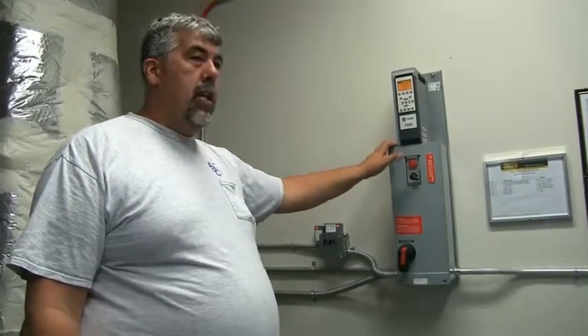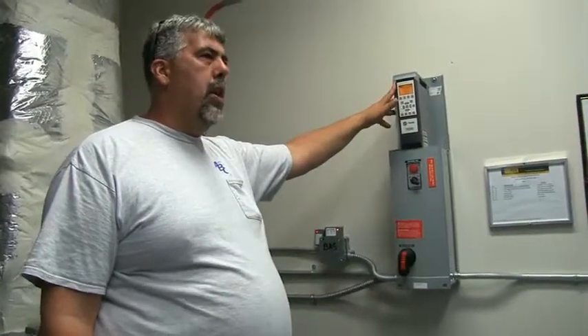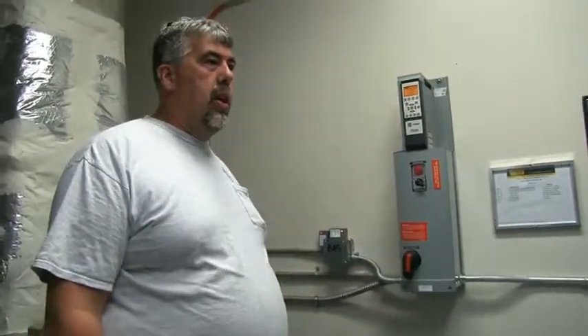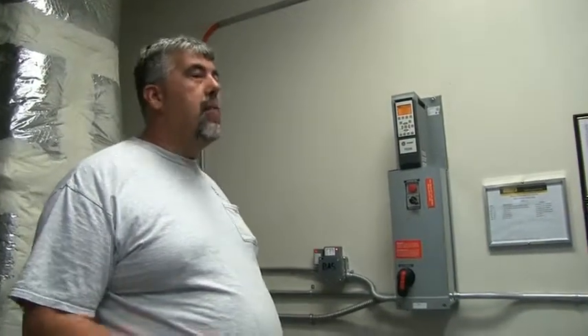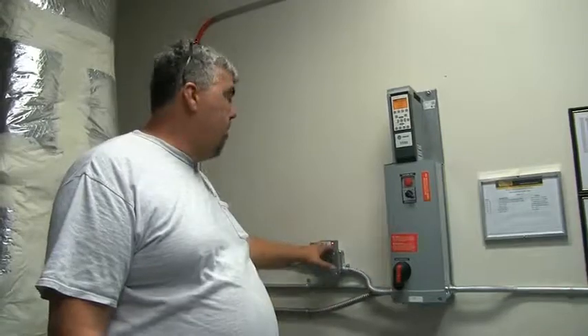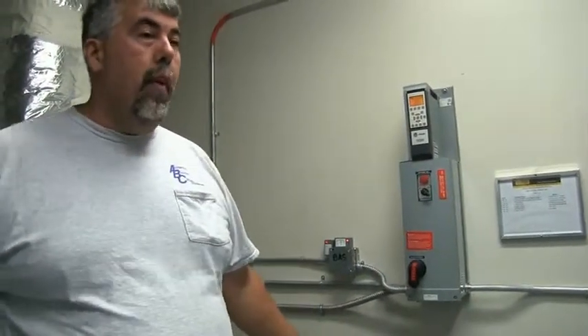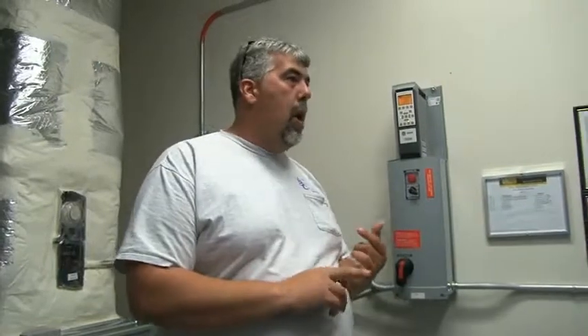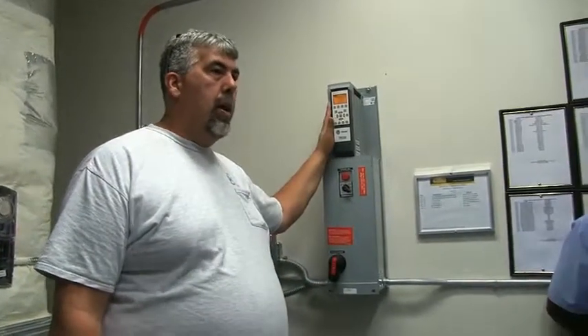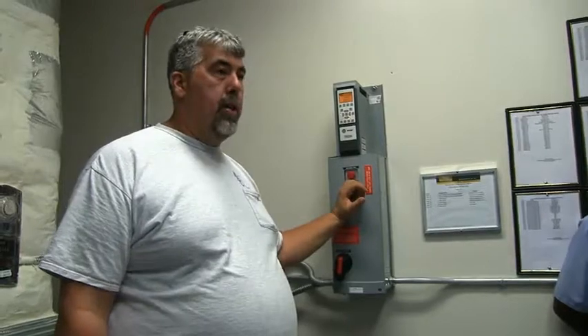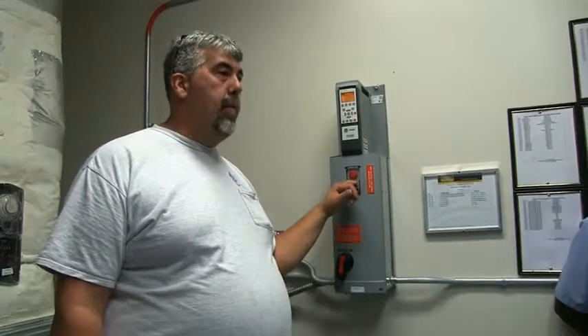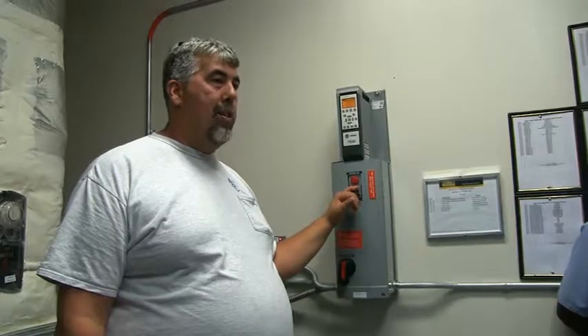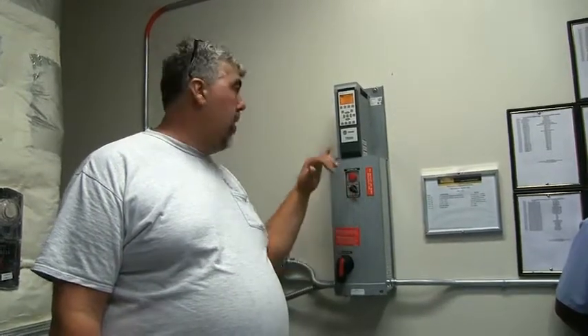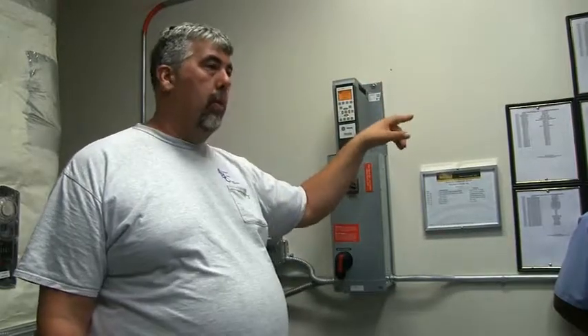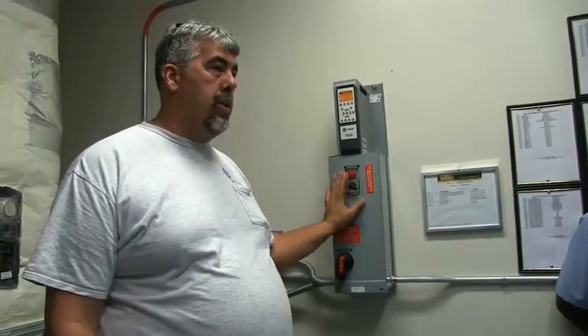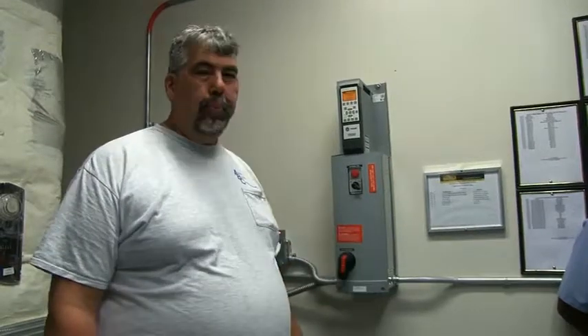Right. So like I said, you'll come in here and you'll see on the drive usually an alarm 60, I believe it is, which says it's a loss of contact closure. The safety contact is open or something along those lines. That's either these, and if these are not the problem, then it's a fire alarm issue. That's the only thing that does that safety circuit. And they are the only ones that will not allow you to put this in bypass. So if your fire alarm's having an issue and you want to put it in bypass, you're going to have to either take the wires off or try to find a way to override it at the panel to be able to put this thing back online, because it will hold it out.